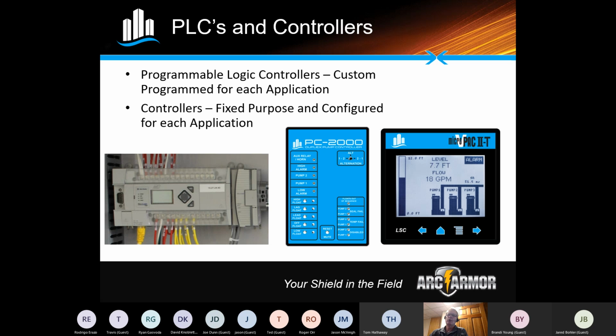So couple things here. So this one on the left is an Allen Bradley Micrologix controller, PLC. The ones in the middle are some of what we would call controllers. So it's got a specific purpose. The one in the middle is basically a duplex pump controller off of floats. The one on the right can be up to a triplex using a transducer for control. It can also have float backup, but basically with this controller, you pick and choose how you want it to operate. If you want a duplex, triplex, simplex, all the variables, there's no custom programming that has to be done.